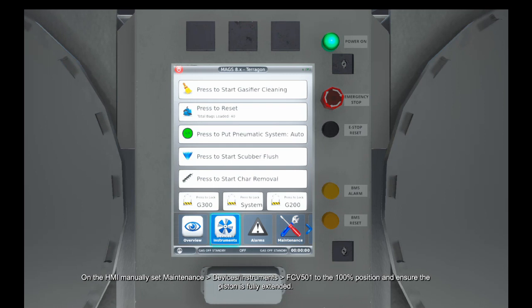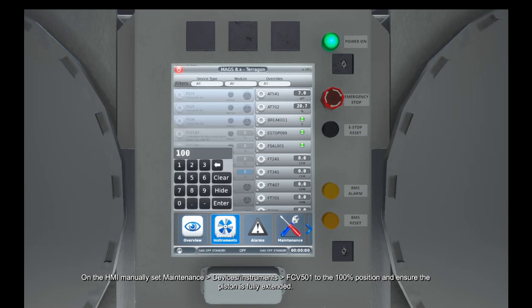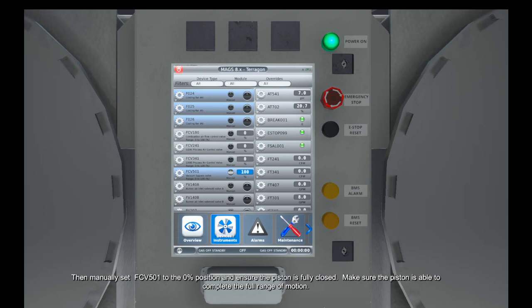On the HMI Devices Instruments tab, manually set FCV501 to the 100% position and ensure the piston is fully extended. Make sure the piston is able to complete the full range of motion.